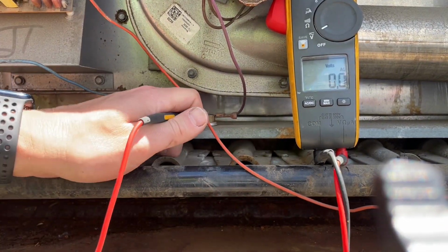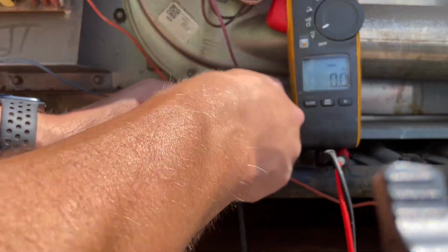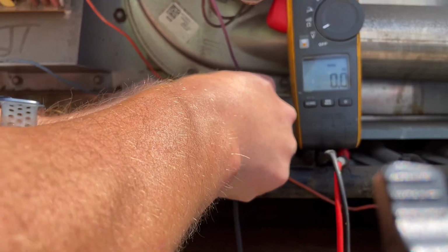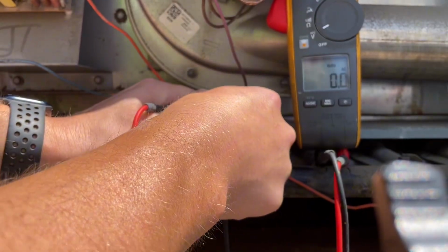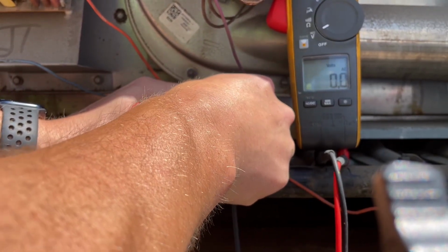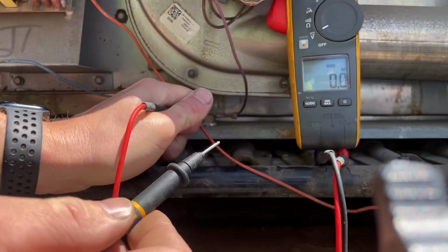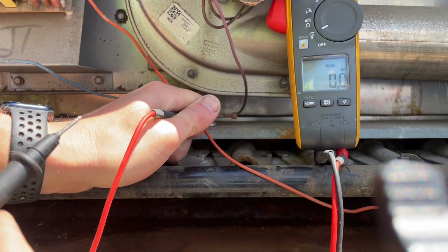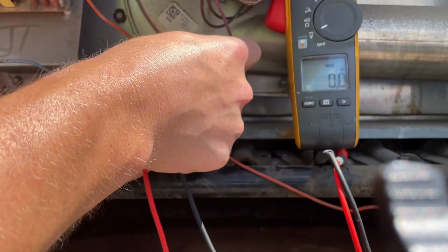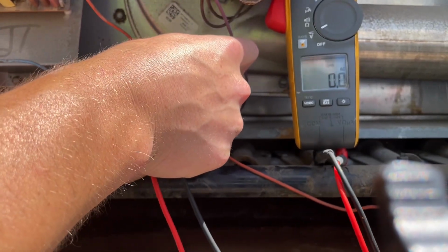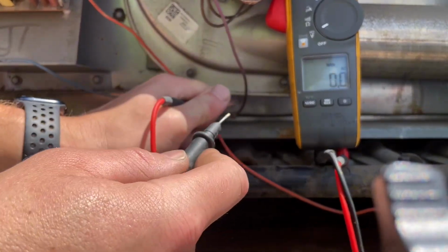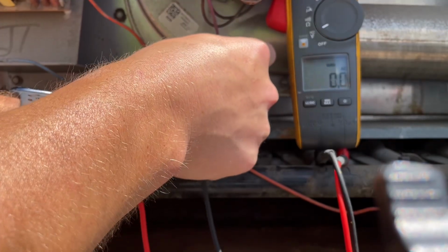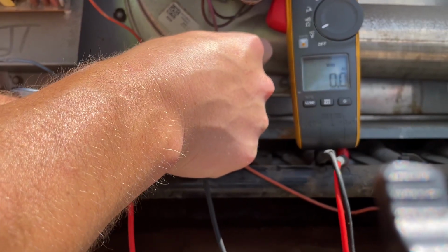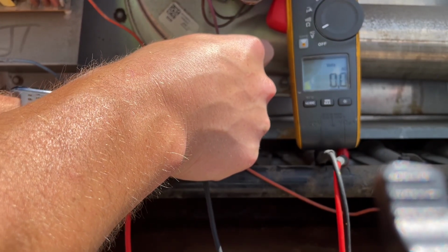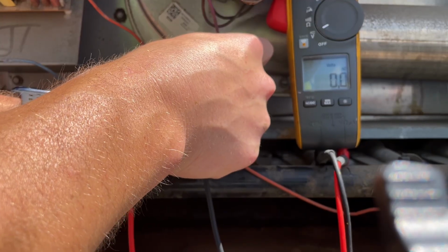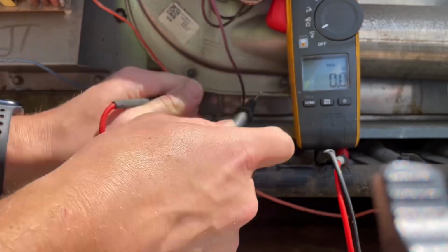You're gonna go across the rollout switch. So either terminal here, either side, we should have 0 volts if it's closed, which we do, but I would double check if I was you and go from one side to ground. So we have one lead here, kind of scratched away any of the rust, and let's get our ground here from our inducer housing. We have nothing. I check your other side, and we have no voltage. So we know that our limit switch, which is before this rollout in series, probably has an issue.